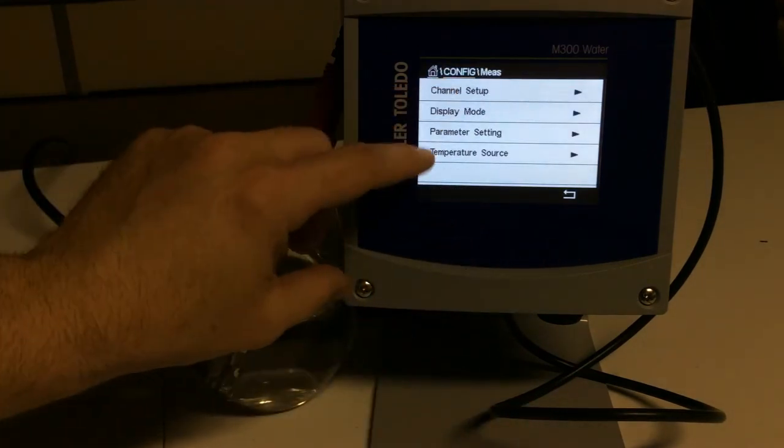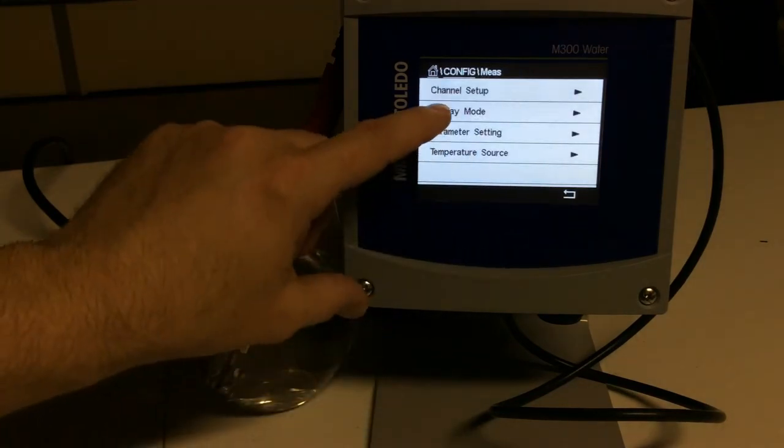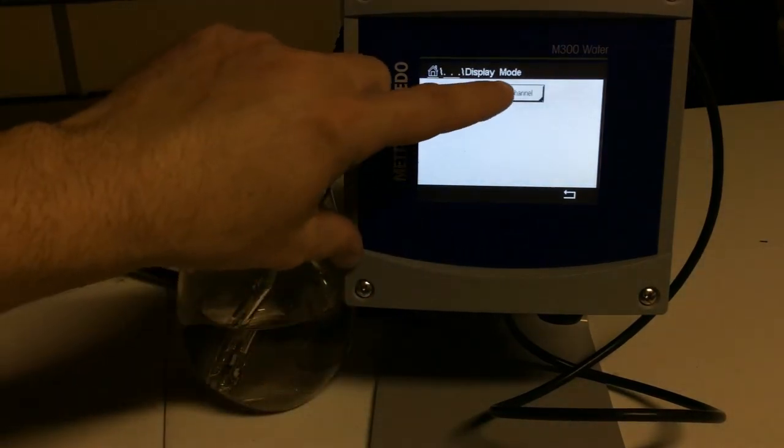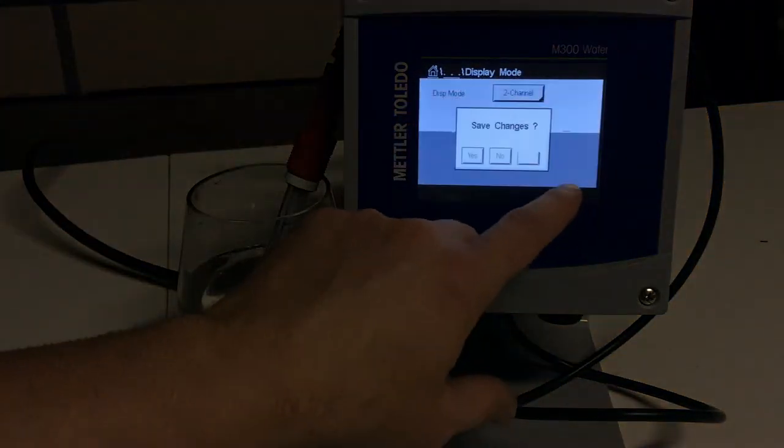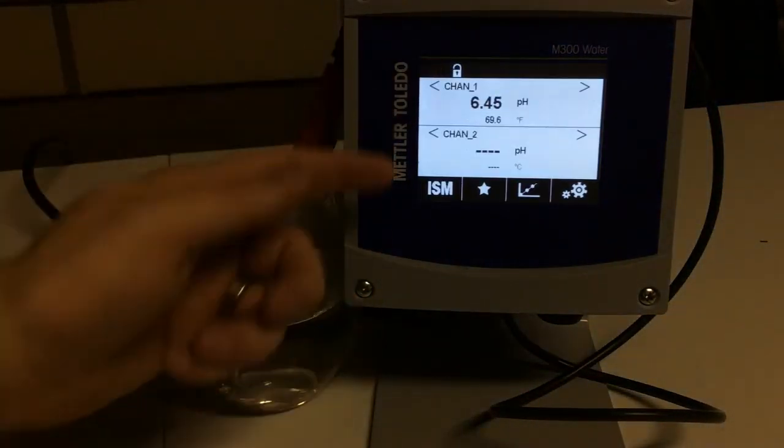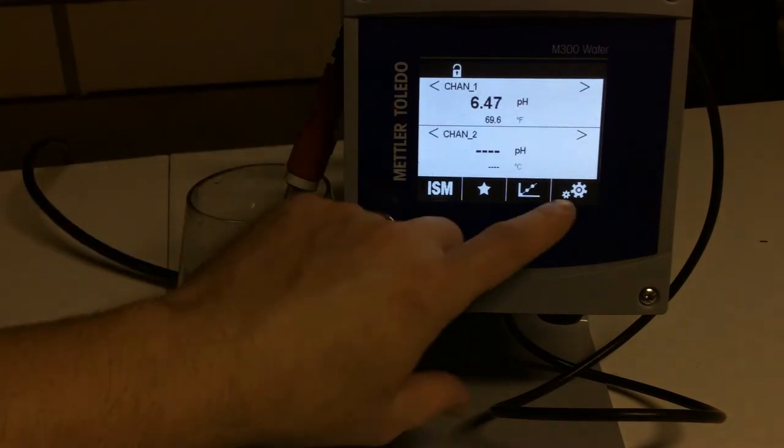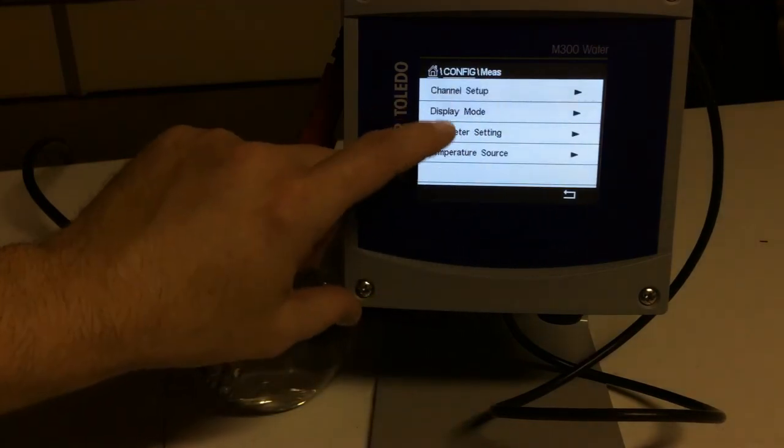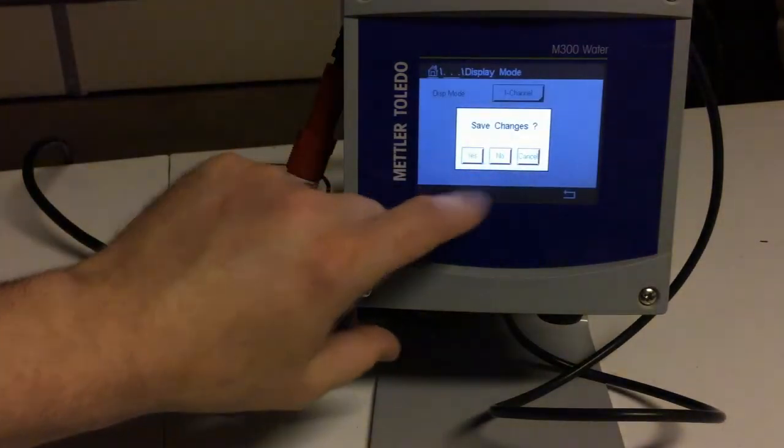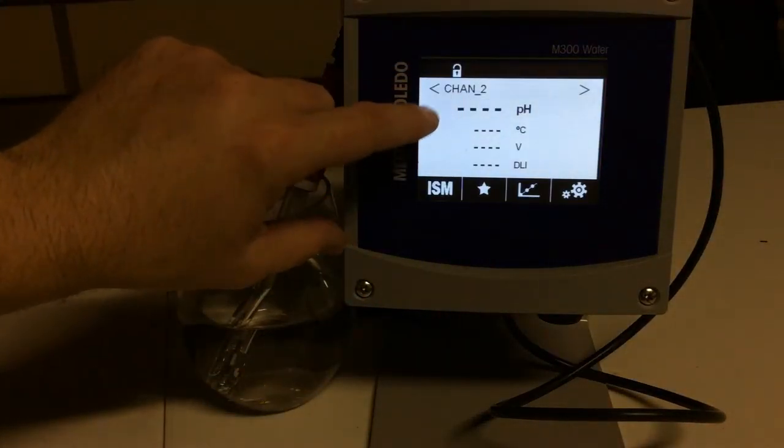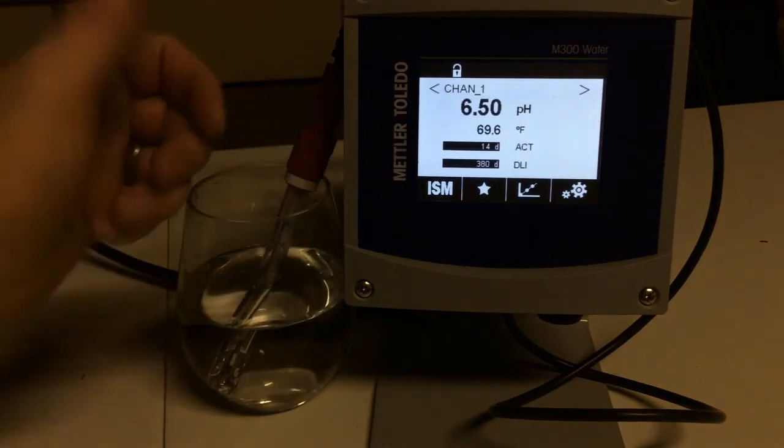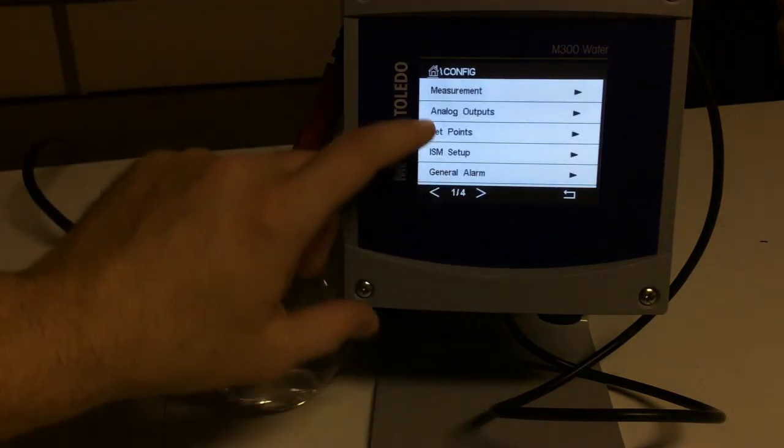So getting back to measurement, that was channel setup. So now we'll go to display mode. I have it set for one channel. If I had two channels, I can do two channels. Come here, let's save. Let's go home. And now I have a split screen that would give both of my channels at the same time. However, if you did not, if you just want to see one channel at a time, we'll save that, yes, we'll come back home. At any point, you can hit these arrow keys and go from channel one to channel two. So it's really customizable how you want to do that.